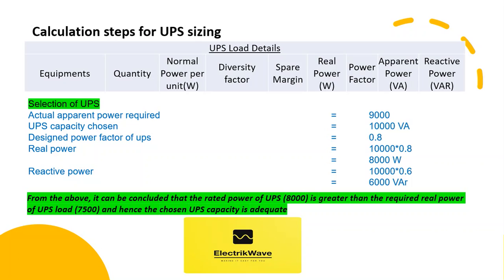For UPS selection: actual apparent power required equals 9000VA. UPS capacity chosen equals 10,000VA. Designed power factor of UPS equals 0.8, real power equals 8000W, reactive power equals 6000VAR. It can be concluded that the rated power of UPS at 8000W is greater than the required real power of UPS load at 7500W, and hence the chosen UPS capacity is adequate.